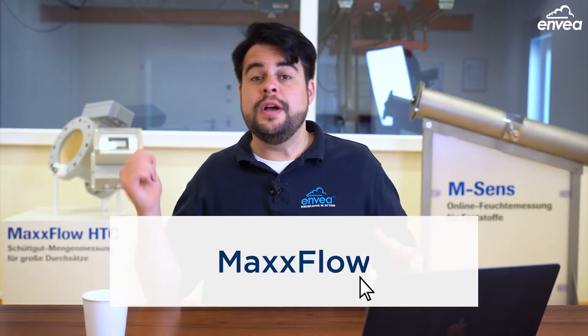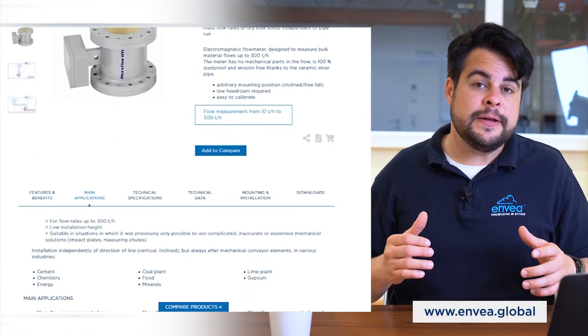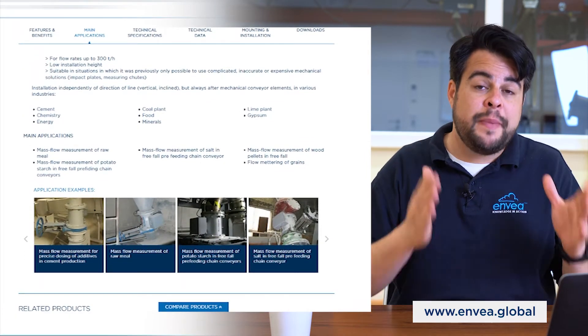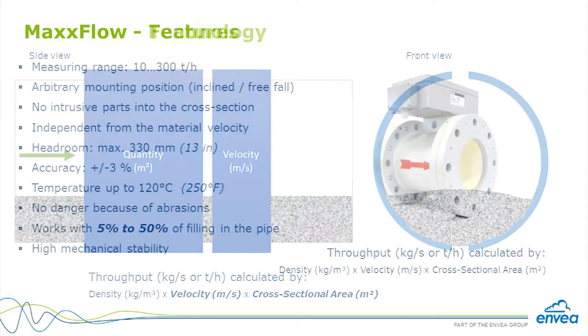And now let's jump to the big brother, the MaxxFlow. MaxxFlow is a mass flow measuring device for bigger range applications, going up to 250 or even 300 tons per hour, while respecting the concentration inside to have a safe application. Inside the sensor, there are two main measurements happening: density and velocity. Using the cross-section information, we can calculate the mass flow.